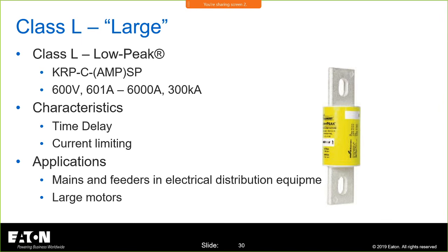Large fans can have long start times. I have changed starter overloads to class 30 a number of times to permit the motor to start without tripping the overload. Yes, if you have that large fan start time, you're going to want to look for a different fuse. In fact, I had that problem on my Marshall half stack. I put a fast-acting fuse in it and I would turn it on and it would open because there's a transformer in there, and the inrush current. I just could not find the right fuse for my application. Actually, I just used whatever I had in my lab. So I went down to the distributor and got the right fuse. I will send you that link for the Bussmann SPD. I'll include that before we get off.